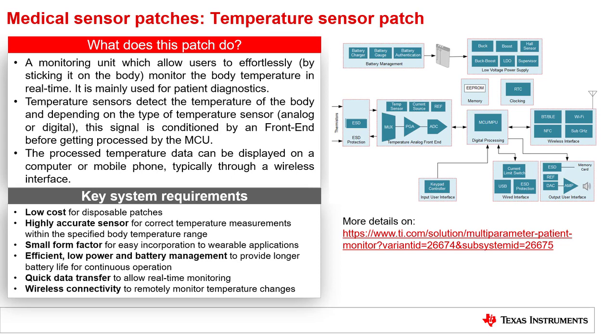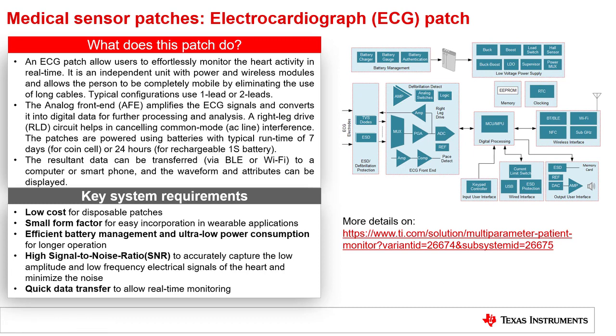An ECG patch allows users to effortlessly monitor the heart activity in real time. It is an independent unit with power and wireless modules, allowing the person to be completely mobile by eliminating long cables. Typical configurations use one or two leads. The analog front end amplifies the ECG signals and converts them into digital data for further processing. An RLD or right leg drive circuit helps cancel common mode AC line interference. The patches are powered using batteries with a typical run time of seven days for coin cell or 24 hours for a rechargeable 1S battery. Resultant data can be transferred via BLE or Wi-Fi to a computer.